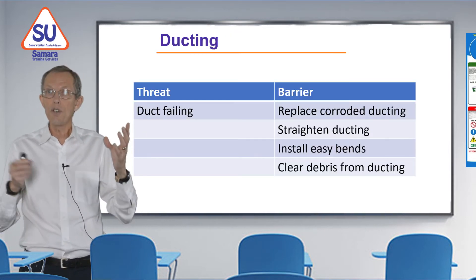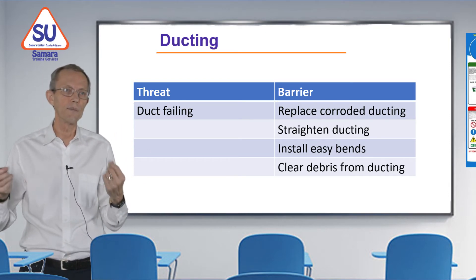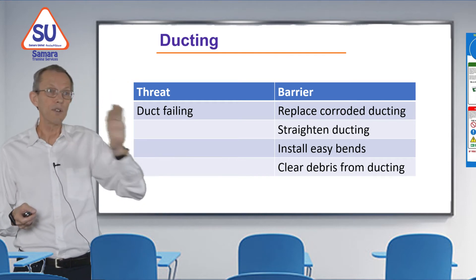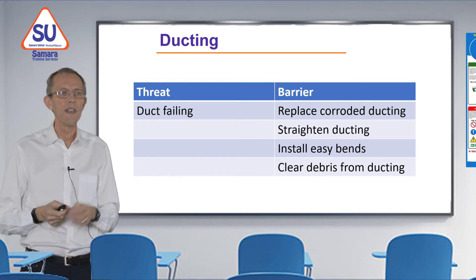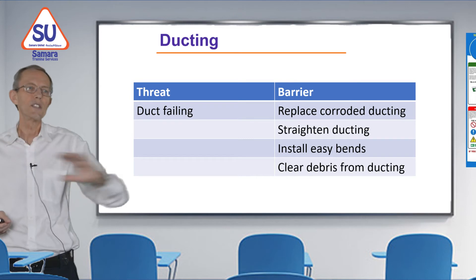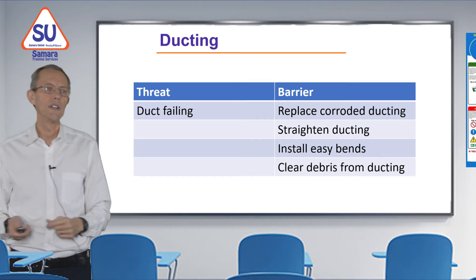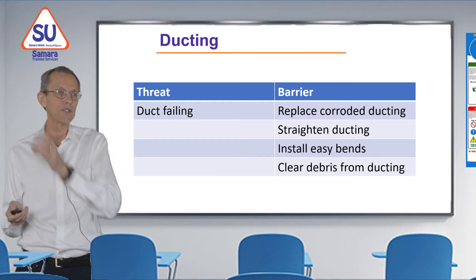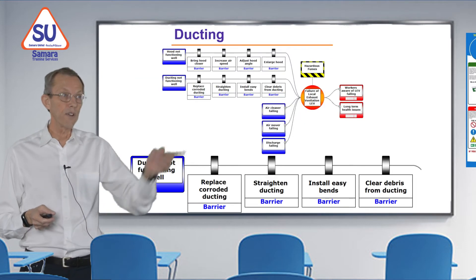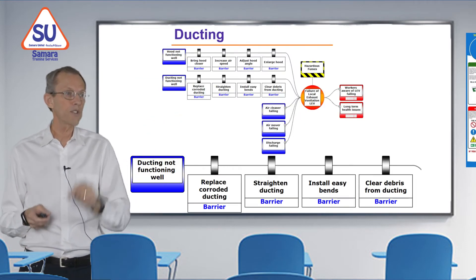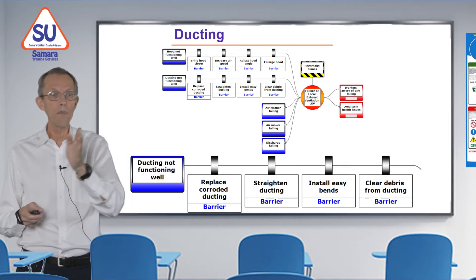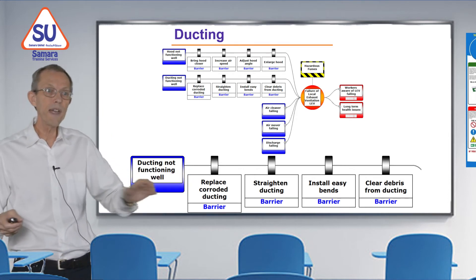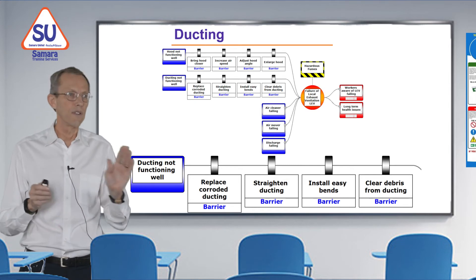Moving on to ducting: if the ducting fails, it could be because it's corroded — we could replace it. It could fail because there are too many bends, making it difficult to pull air flows through; so we could straighten the ducting or replace sharp bends with gentle, easy bends. Lastly, we can clean out accumulated debris — dust or anything else in the ducting. On the diagram, the second threat line shows: ducting not functioning well, and four barriers — replace corroded ducting, straighten the ducting, make smooth easy bends, and clear the debris.